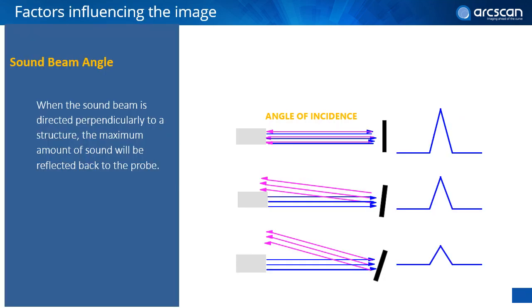When we start to do imaging, there are a few factors that influence the quality of the images. One of the most important factors is what we call the angle of incidence. For the best quality scan, the probe needs to be perpendicular to the structure you're evaluating. This way, you have maximum feedback reflected back to the probe. The more perpendicular to the structure, the stronger the echo, the higher the peak, the brighter the surface, and the clearer the overall image.